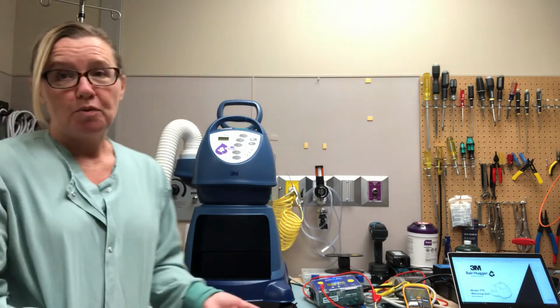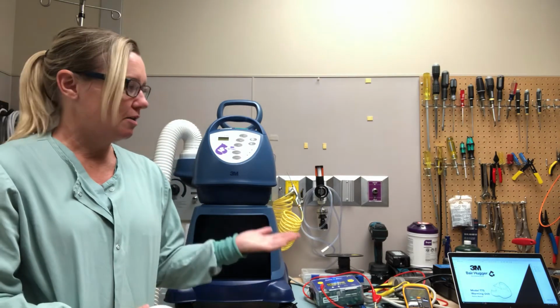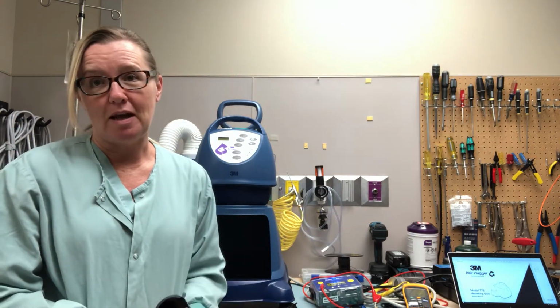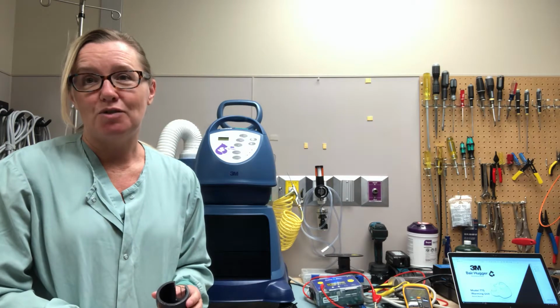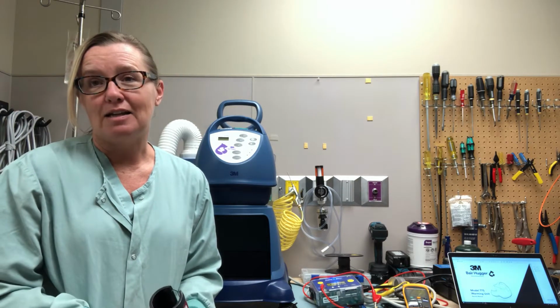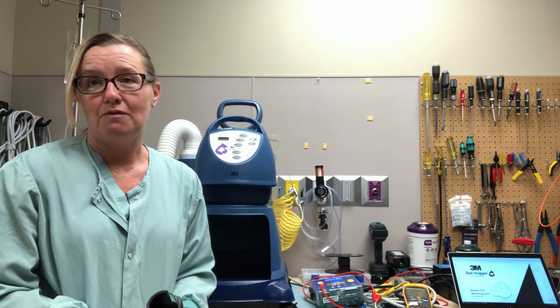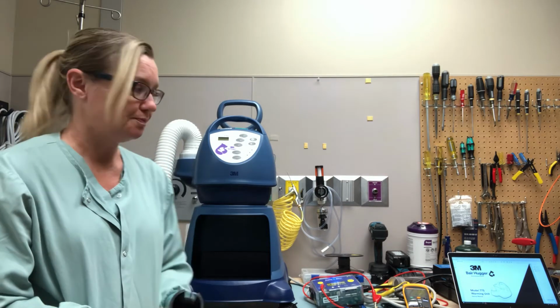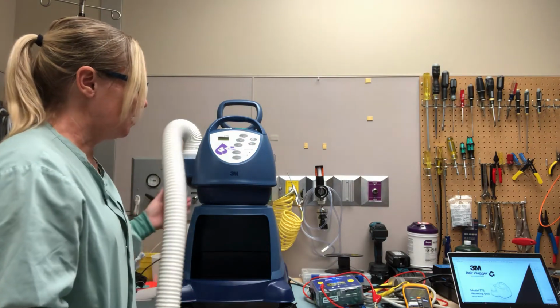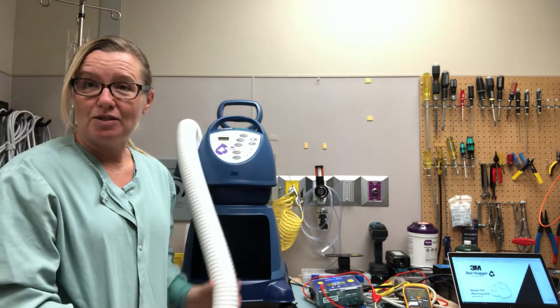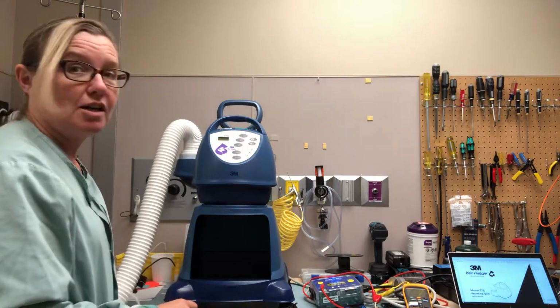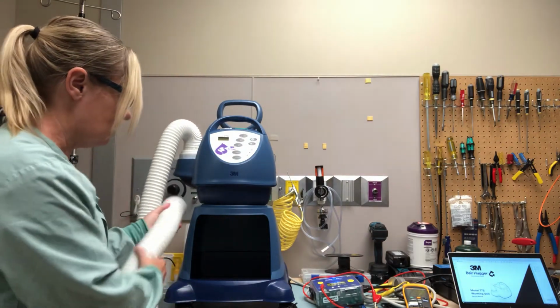So let's get started with the preventive maintenance. First of all, the service manual is always on my laptop. I've been doing this for many years, but I still need to reference the service manual for most preventive maintenances. I'm not going to remember exactly what the instructions are every single time, so it's best to just review your preventive maintenance instructions before you start. And we're going to start with the electrical safety test, which is done on all medical devices, or the majority of them.